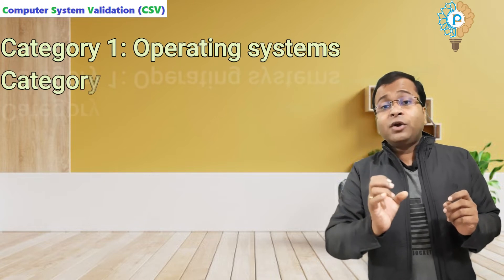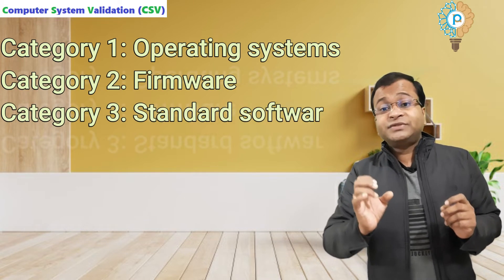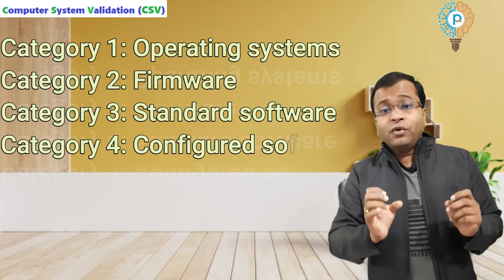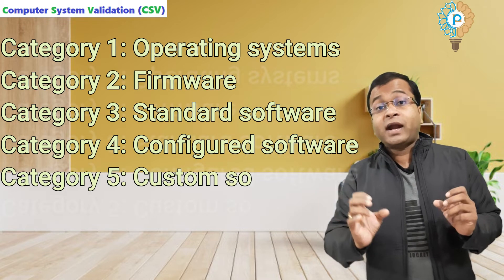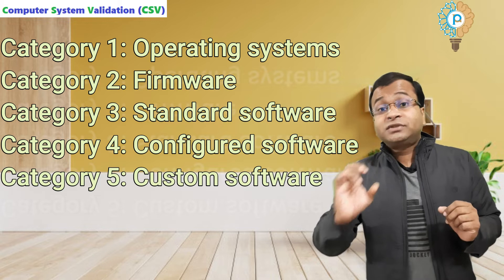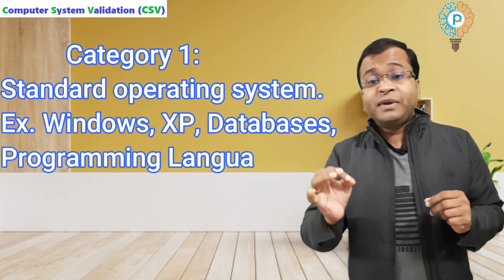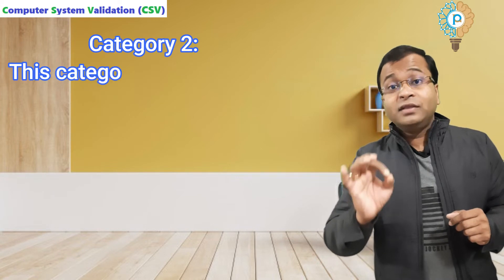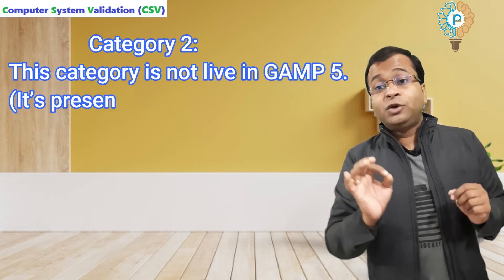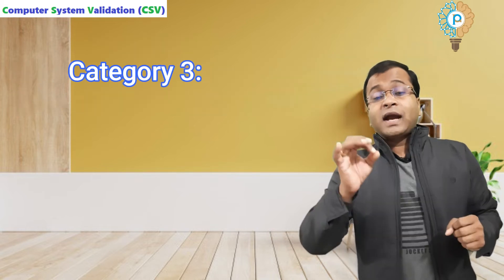Category 1 is the operating system. Category 2 is the firmware. Category 3 is the standard software. Category 4 is the configured software, and Category 5 is the custom software. Now I am explaining each category. First is Category 1: standard operating systems like Windows XP, database, and programming languages. Category 2 is not live in the GAMP 5 guideline; it was present in the old version of GAMP 4.